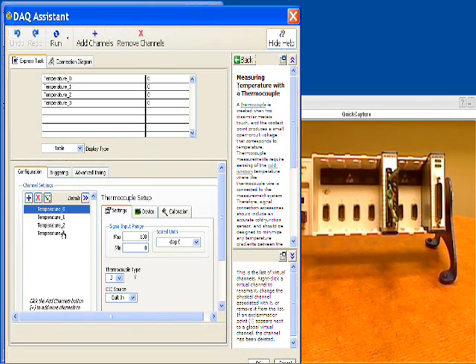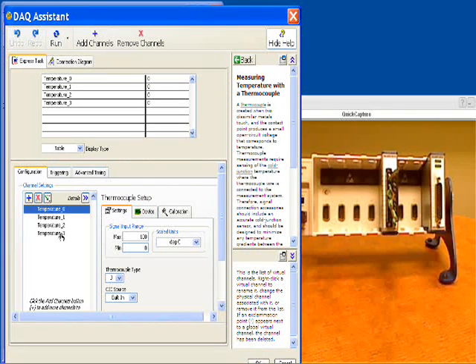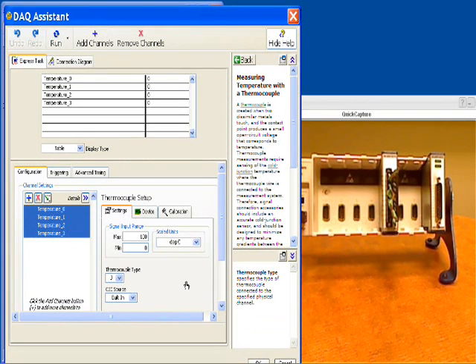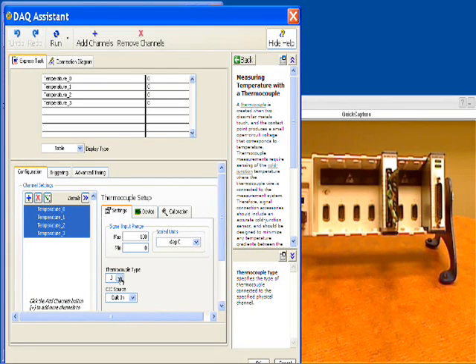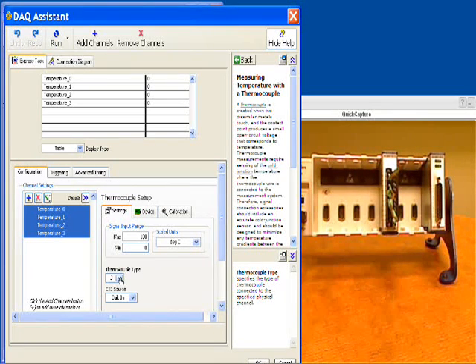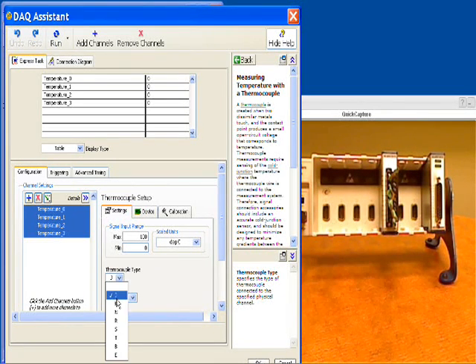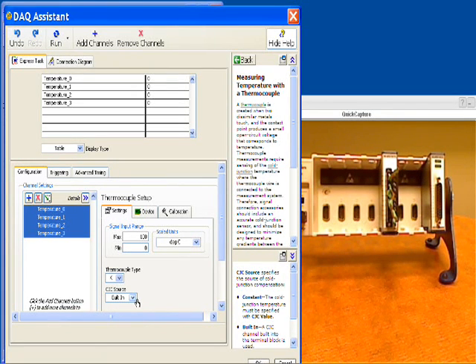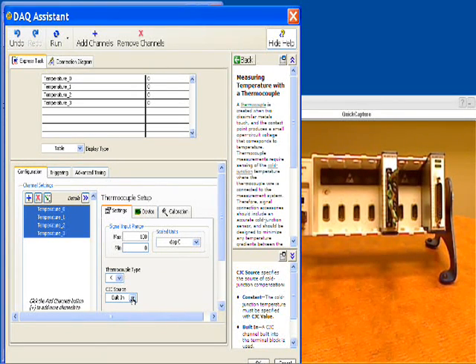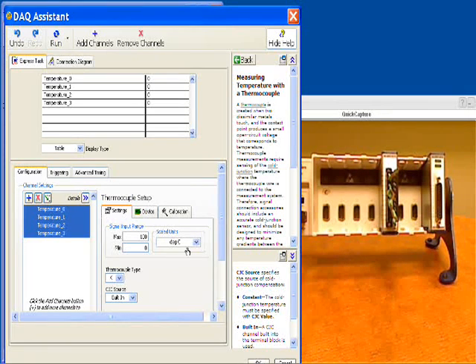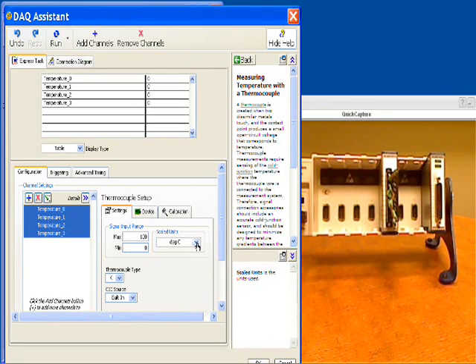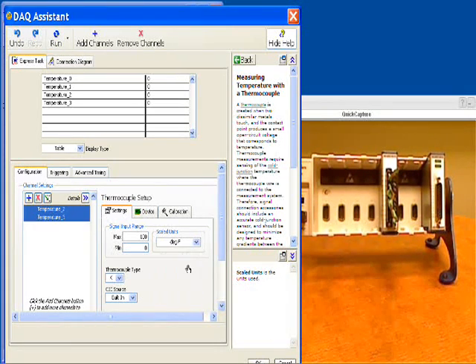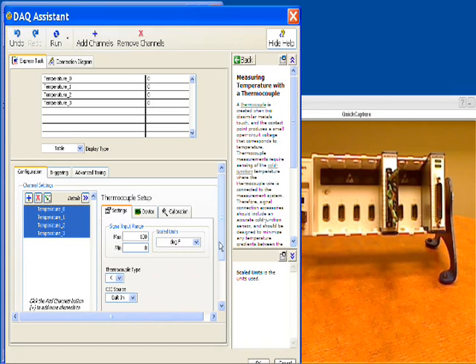Now in my configuration screen, I'm going to select all four thermocouples so I can configure them all at the same time. This is a K-type thermocouple so I'm going to use the pull-down, select K-type. Notice that the cold junction compensation or CJC source has been automatically selected as built-in, which is good. I'm going to change my scaled units from degrees C to degrees Fahrenheit.